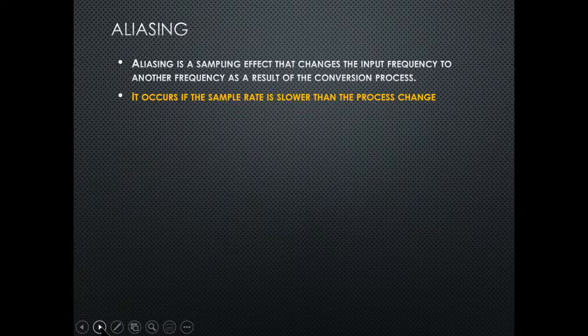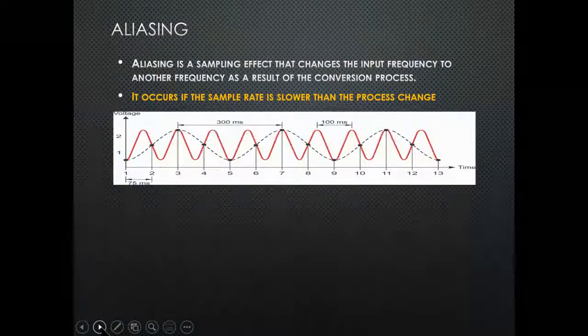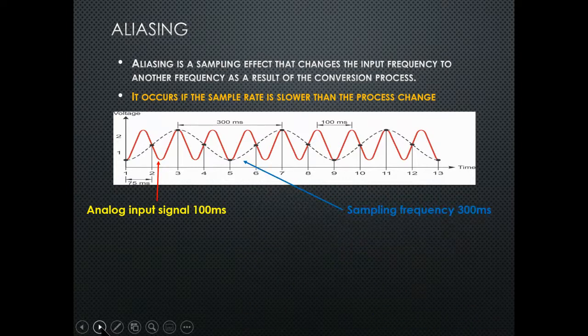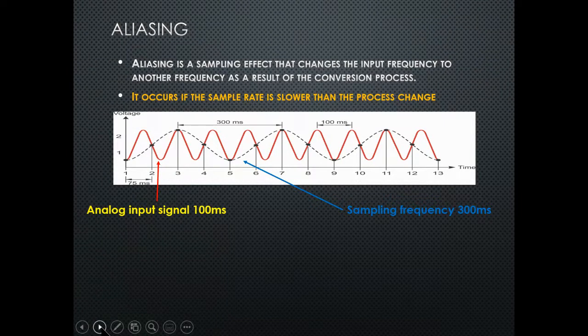To avoid aliasing, you need your scan time at least twice the rate of the incoming signal — two times the sample rate. For example, with an analog input signal shown in red going up and down, if the sample frequency is 300 milliseconds you can see how many signal pulses you're missing. The sample frequency is shown as a dotted line — that's how fast you're scanning the transmitter.